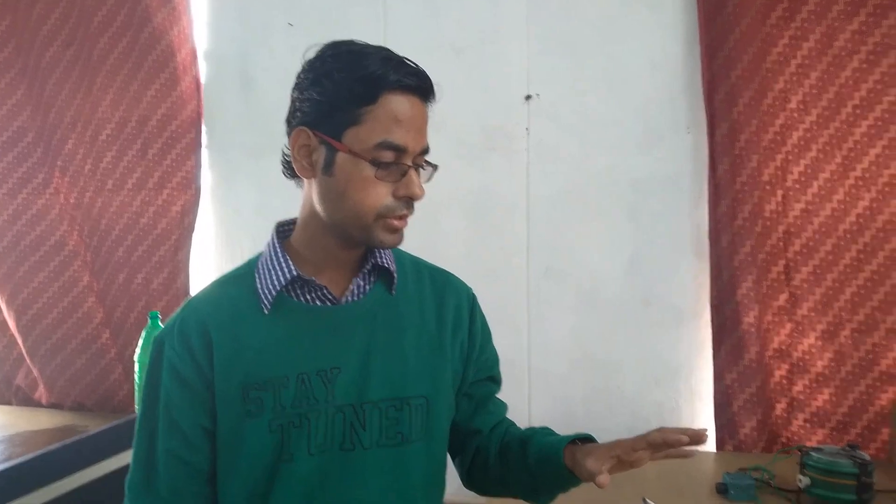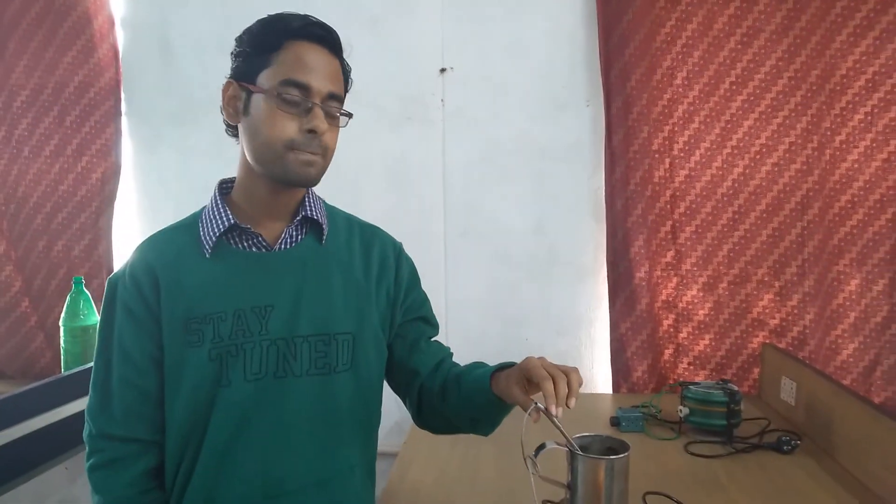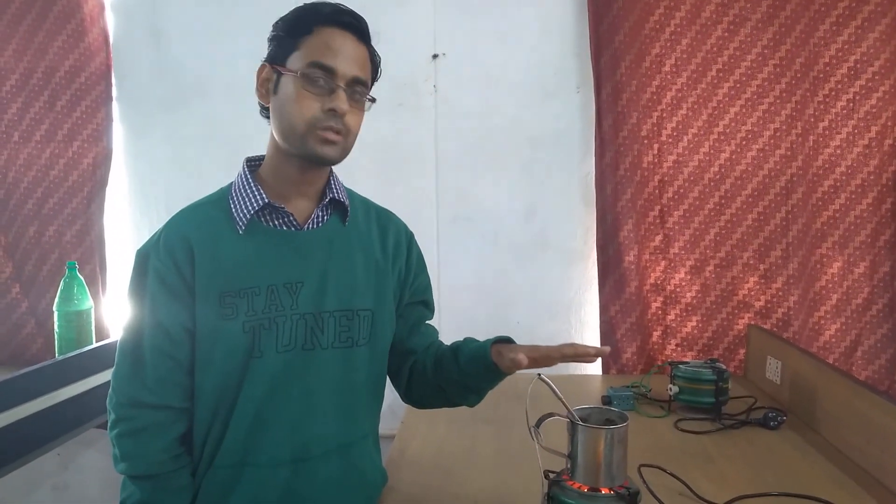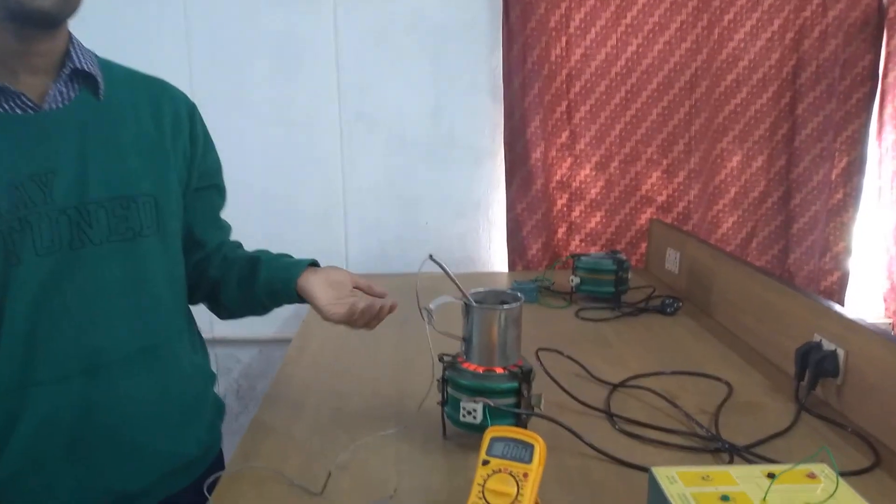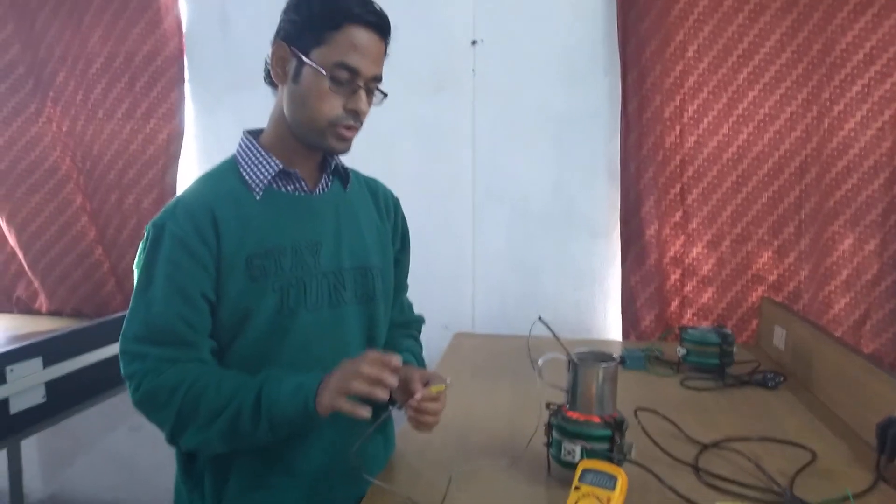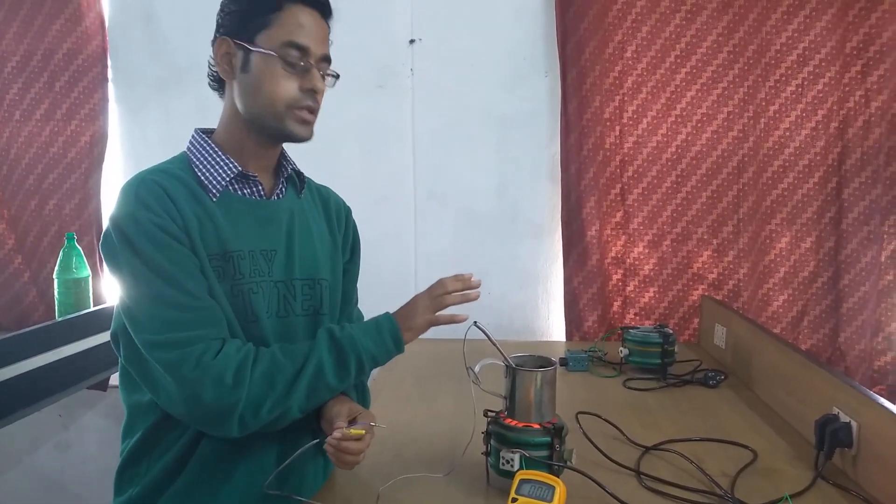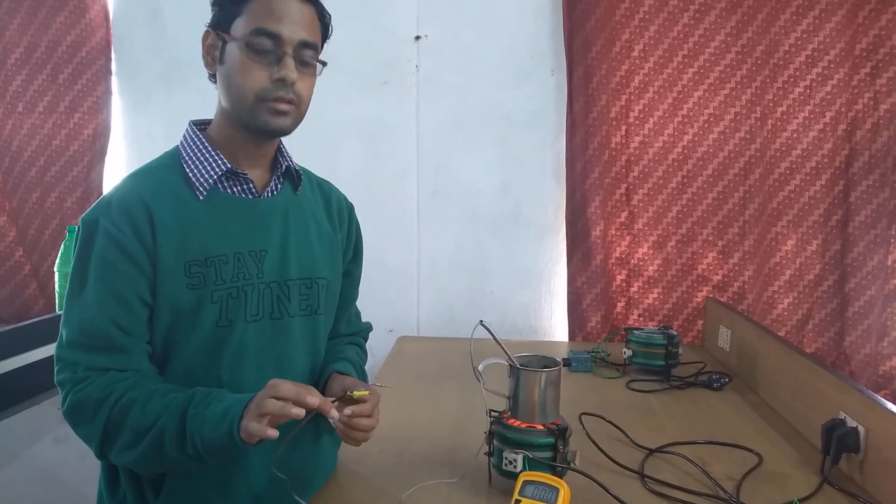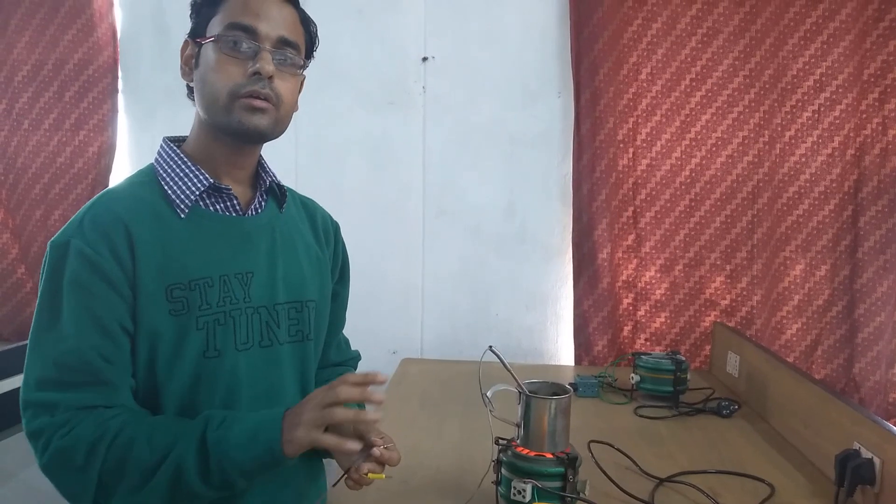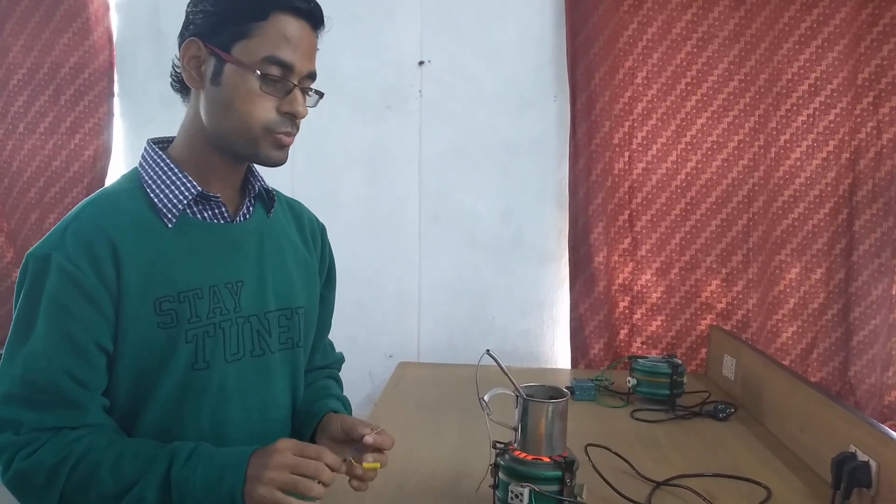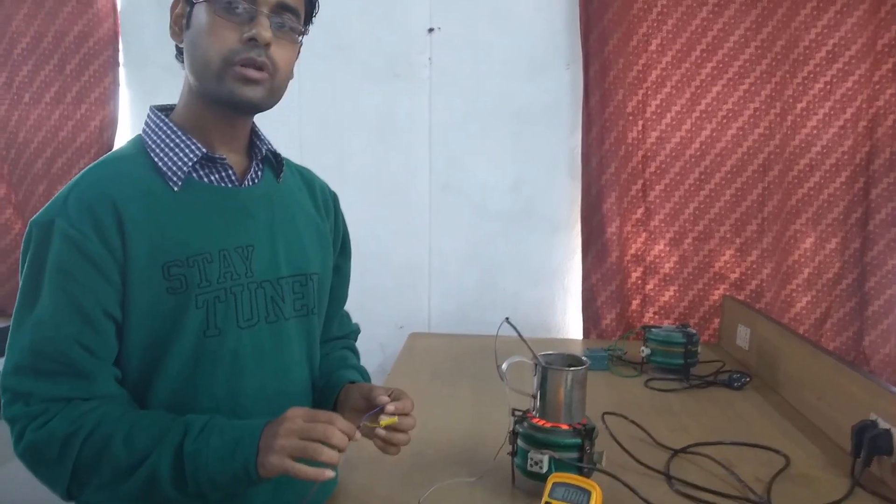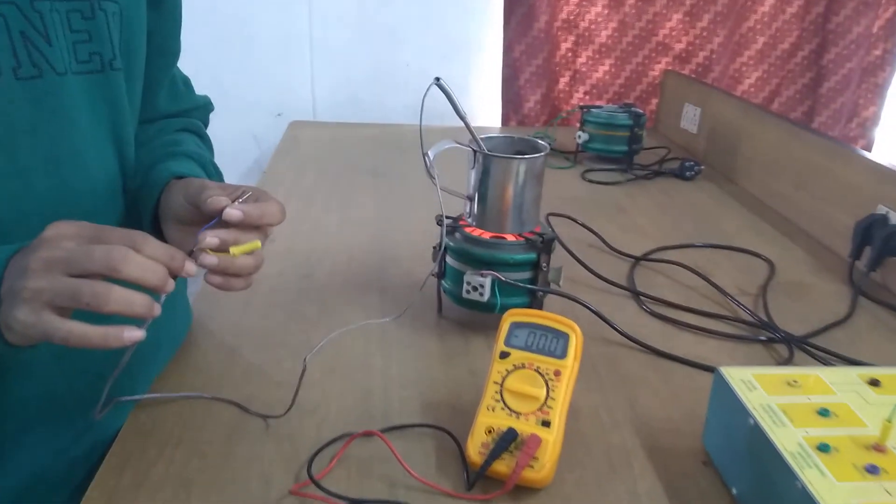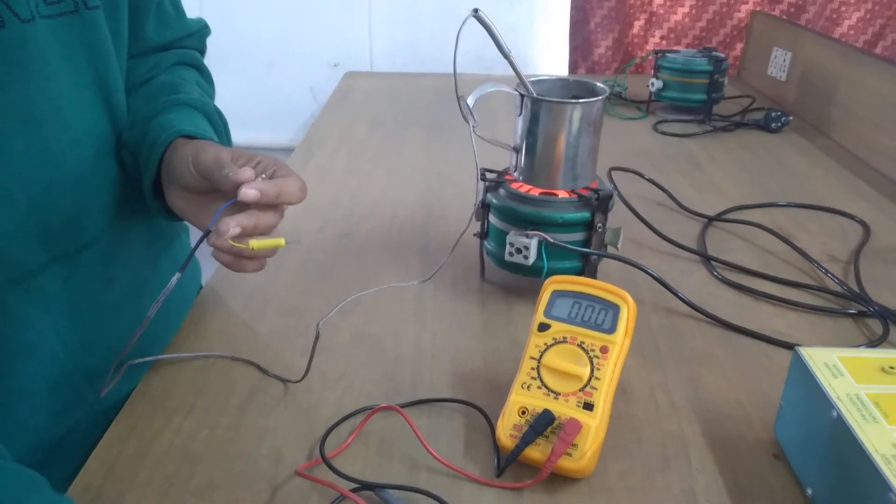So here we have dipped the thermocouple in a process tank. You can think of this as a process tank. So right now this beaker is containing water and we have heated it up. So what we want to do is now we find that the hot junction is at process temperature and the cold junction is at ambient. So we want to look at the variation of output voltage as provided by this particular thermocouple. Note that this is a J type thermocouple which means that the constituents are made of iron and constantan.